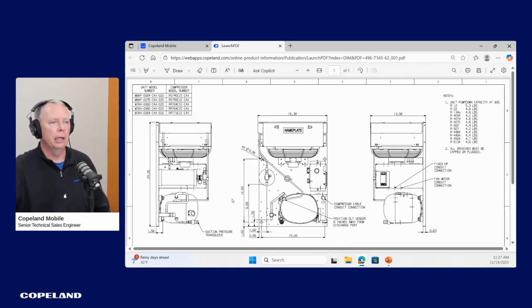One thing we talked about earlier was the identifiers, so you can look here and see what the unit looks like, the transducer location. It comes with a base valve, an electronic unit controller, and this is a single fan unit. But back to refrigerant charge, on the right side of the drawing you'll see the pump down capacity at 90%. This takes into account the receiver capacity as well as some capacity in the condenser coil.